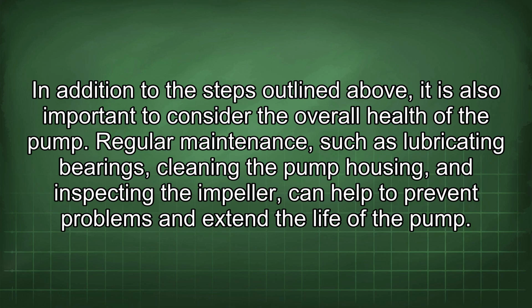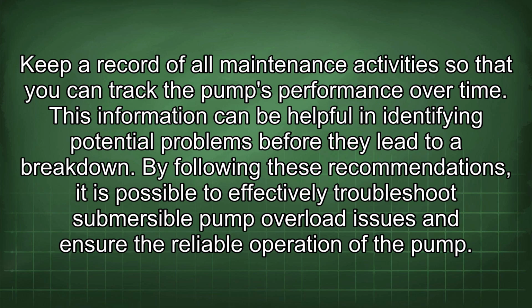In addition to the steps outlined above, it is also important to consider the overall health of the pump. Regular maintenance, such as lubricating bearings, cleaning the pump housing, and inspecting the impeller, can help to prevent problems and extend the life of the pump. Keep a record of all maintenance activities so that you can track the pump's performance over time. This information can be helpful in identifying potential problems before they lead to a breakdown.